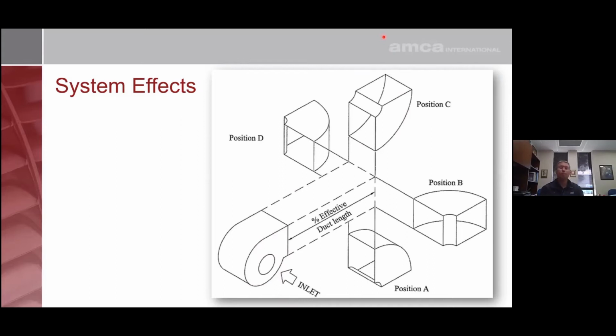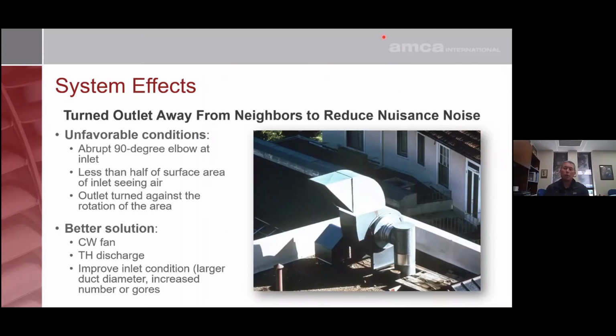So if we look at some field pictures, we can talk a little bit about this. Here we have an upblast fan, throwing air upward. We have a position C elbow, so air hugs the outside of the volute shape, deadheads against the position C elbow, has to get re-accelerated out. There's going to be losses associated with that. Don't have a straight run of ductwork after the fan. That creates a problem because we don't have any static pressure regain. So that's going to affect fan performance.